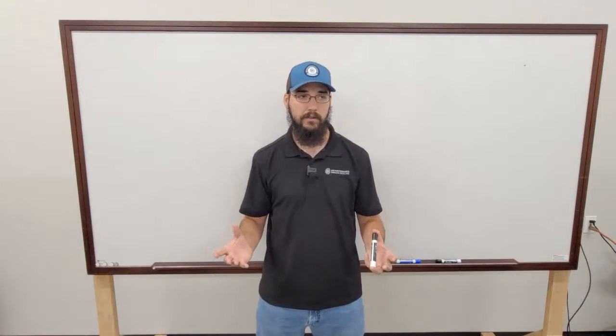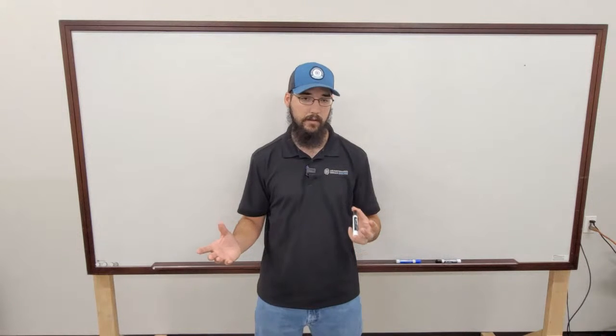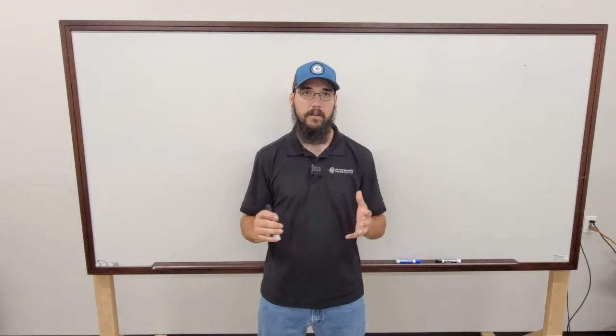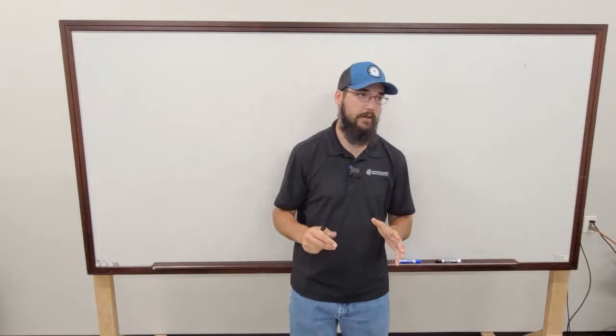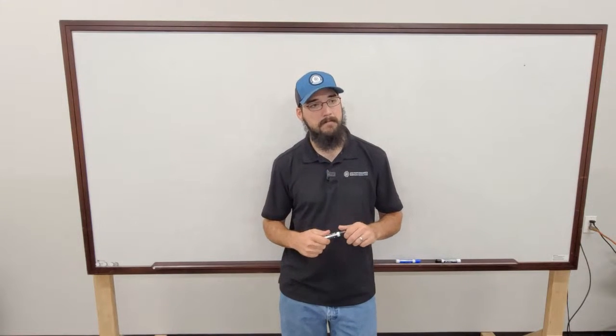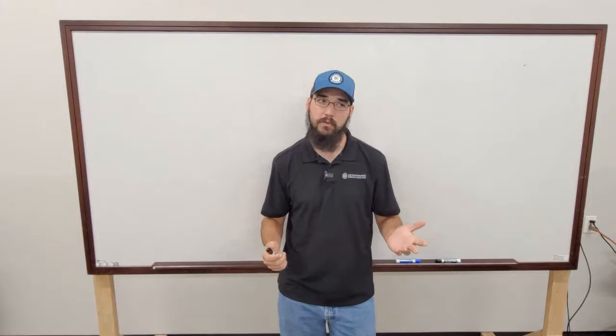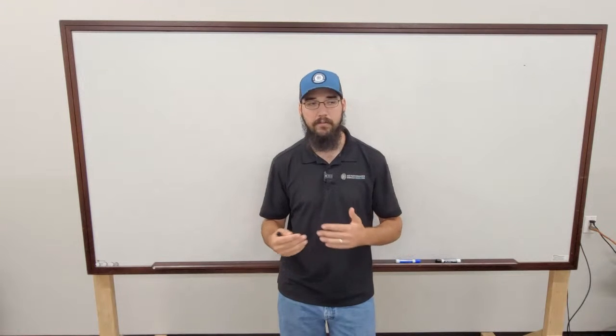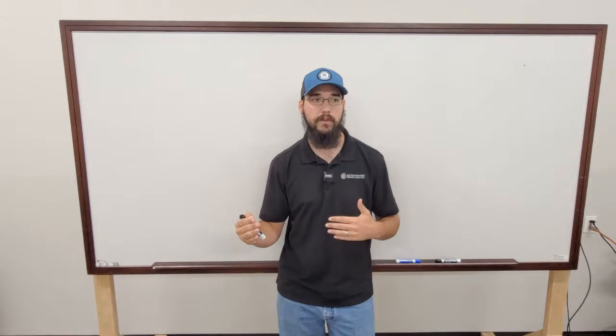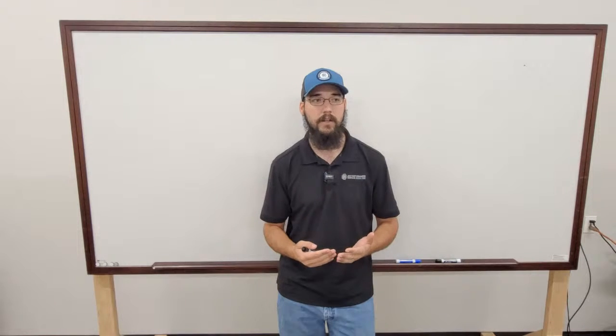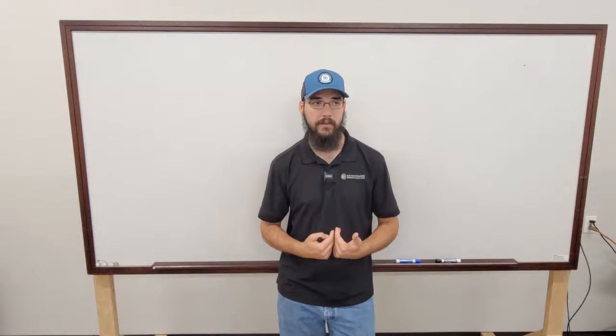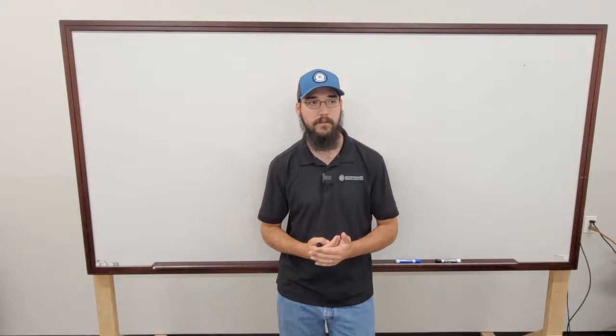If you've got a system that, yeah, I'm not even going to put a parameter on it. From set point, would you want to start maybe a little lower? Well, most of your pull downs, there's not a step 1, step 2 on a pull down. Once you enter a pull down state, whatever that pull down set point is on the current limit, that's what you're going to run.